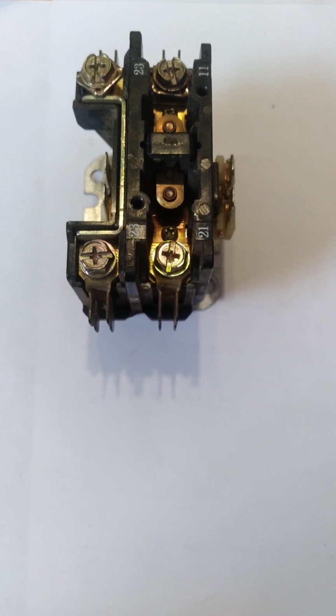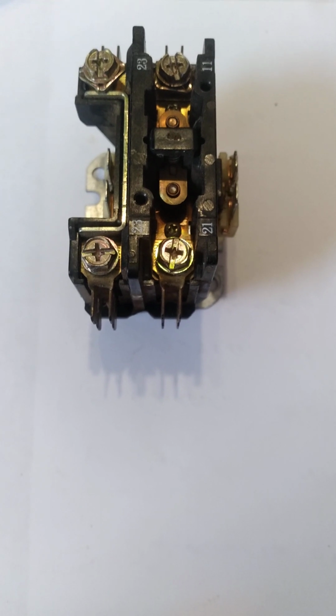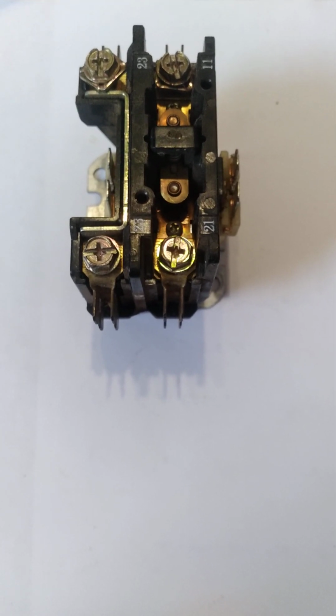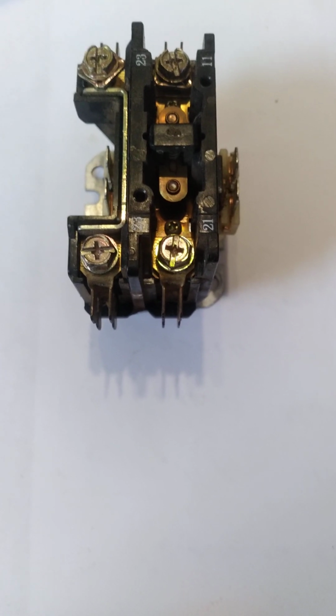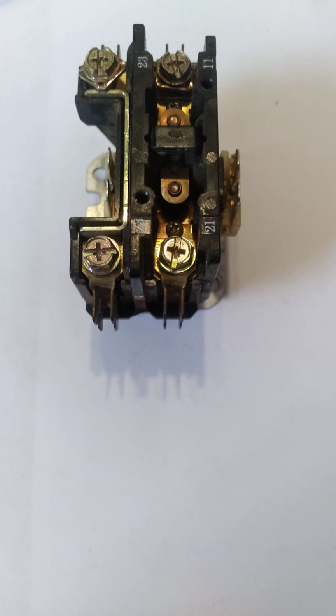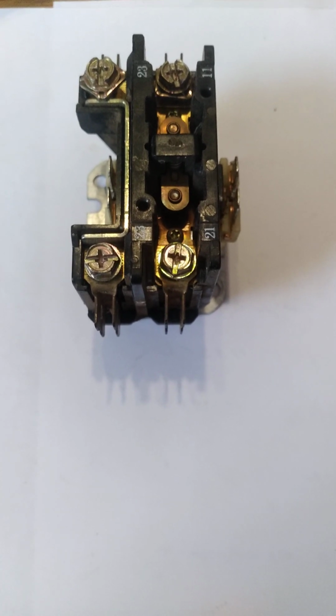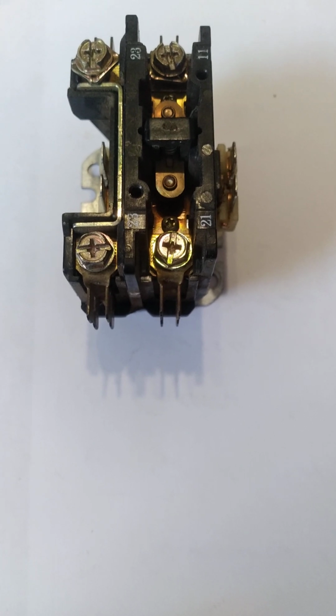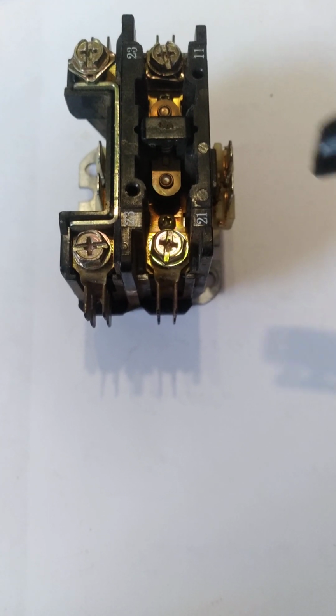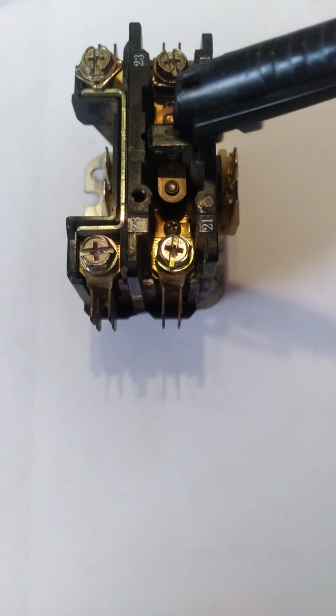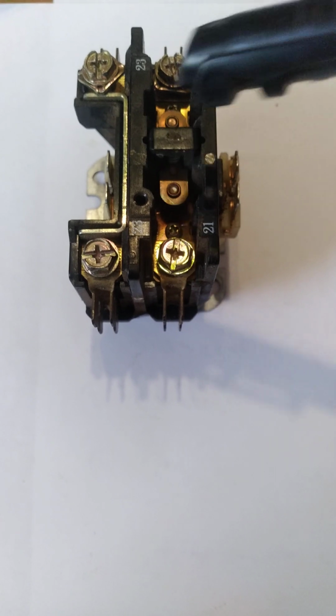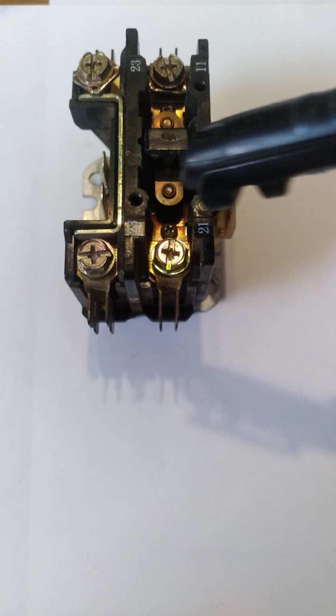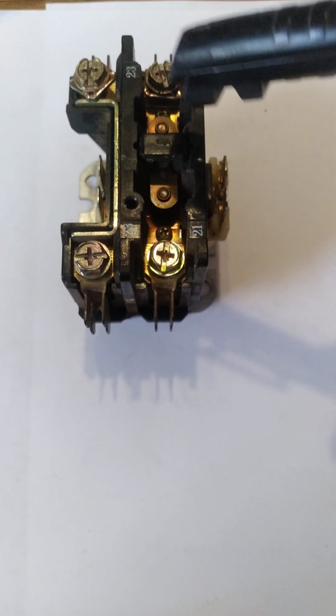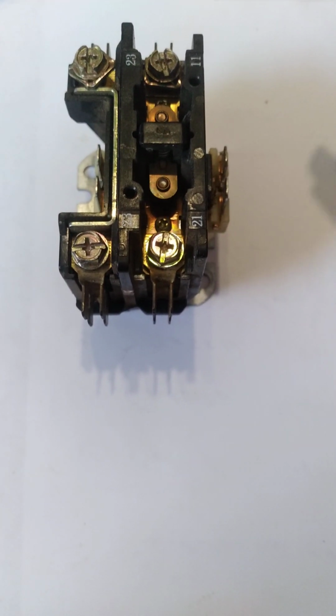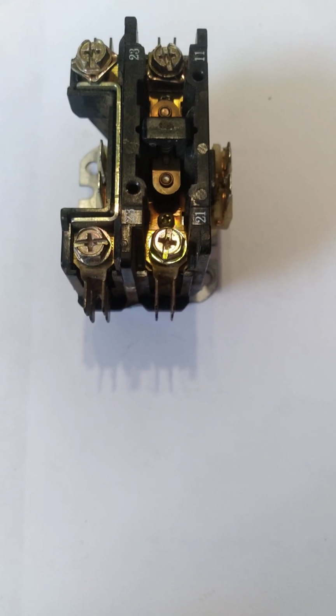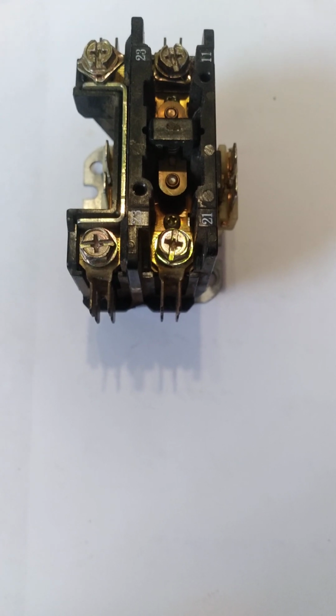When the room is satisfied and the temperature inside of the room is satisfied, say for instance we're trying to reach a set point of 70 degrees. Once we reach 70 degrees and we're finished with this, we do not need the compressor and the condenser fan motor to continue running in most cases. So how do you cut off? Once this is de-energized, boom, this pops back up. Again, boom, this pops back up. When this pops back up, the high voltage will no longer make contact with this side. Hence, the compressor and condenser fan motor, if working properly, may turn off and should in most cases.